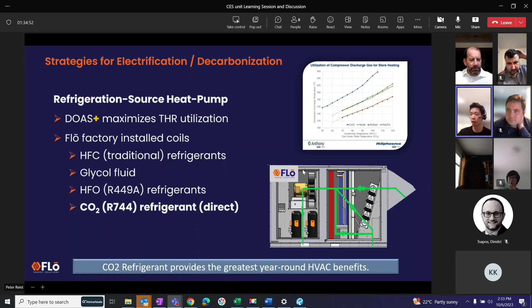Is that correct? So we have two choices. If you're going to give us what we call a chilled water coil, the water to our coil needs to be cold enough to dehumidify. If you can't give us that, then instead you give it to our condenser, and we add compressors and drive that down to what we need, almost like an air source, standard package unit. So you're doing a water-cooled condenser and a water source heat pump in our unit to make that happen if you can't give us cold enough temperatures.